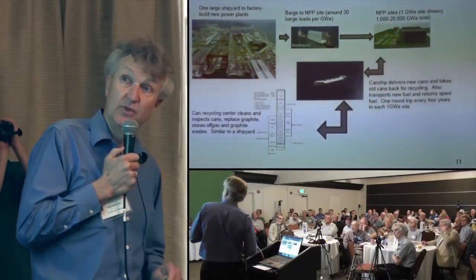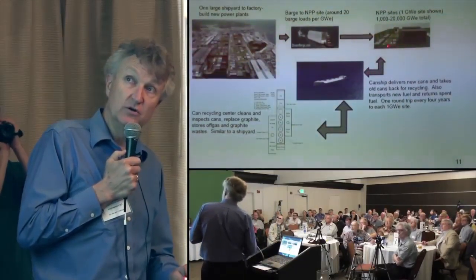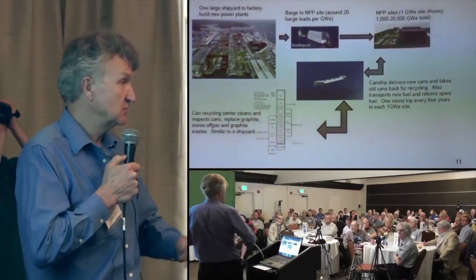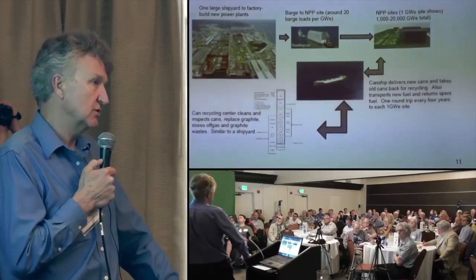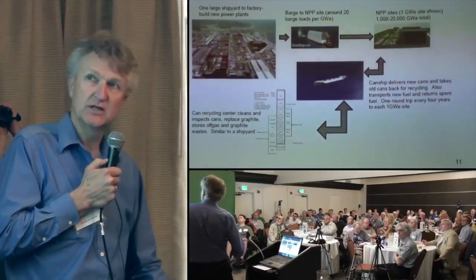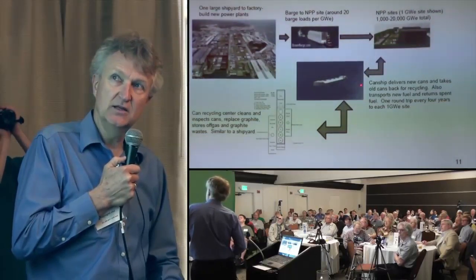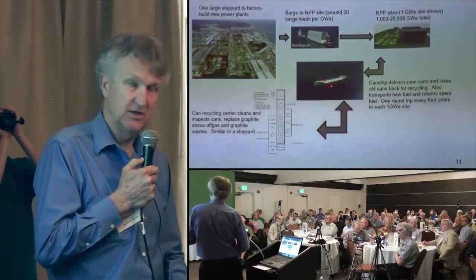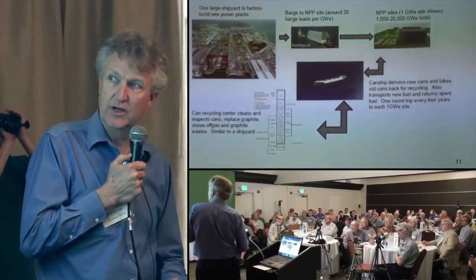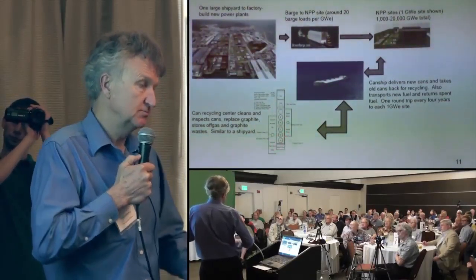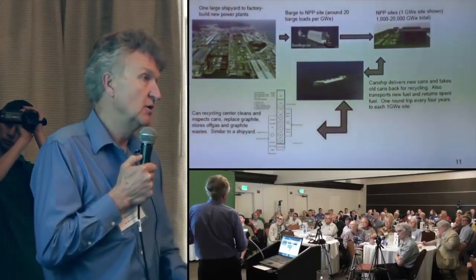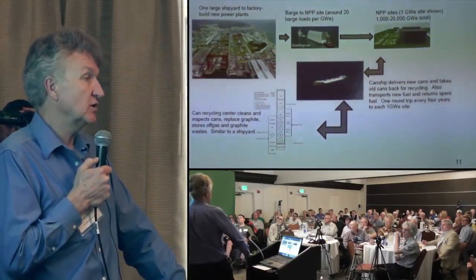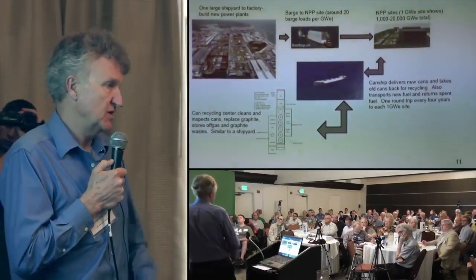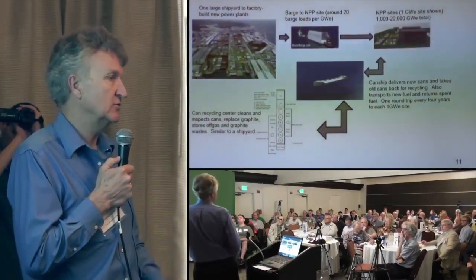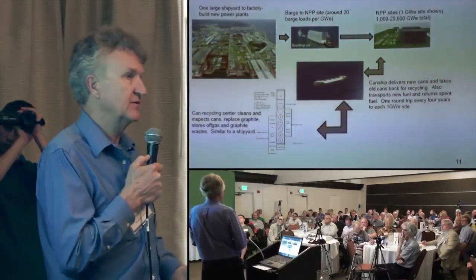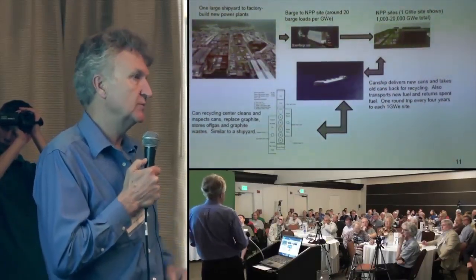Once you've done that, every 4 years we exchange our cans, because we have a graphite-moderated reactor, and the graphite gets neutron damaged, so we have to replace it. We do that with sealed cans put on a can ship, a specially designed ship that hauls them back to a can recycling center, which looks like another shipyard that services about 50 gigawatts electric. We take the cans in, clean them, inspect them, make sure they're still good to go, and ship them back out—or in some cases, like with the graphite, we take the old out and put the new in.